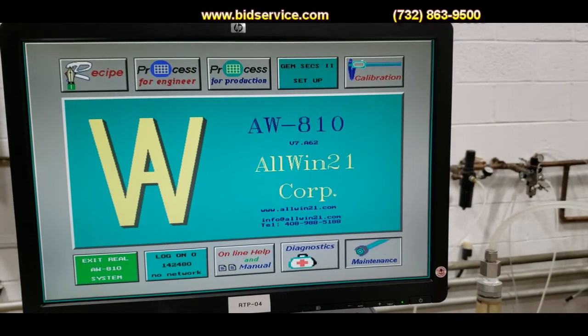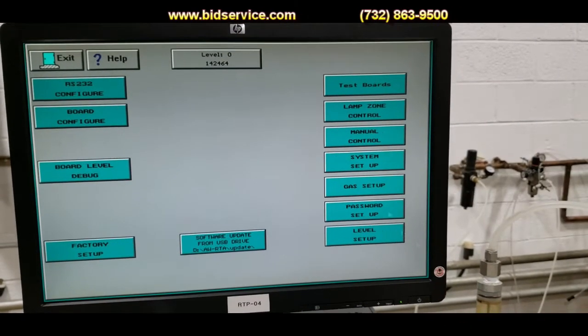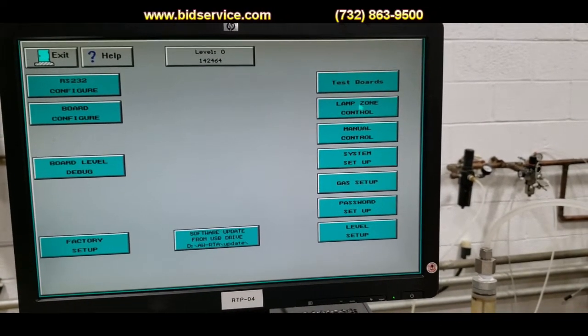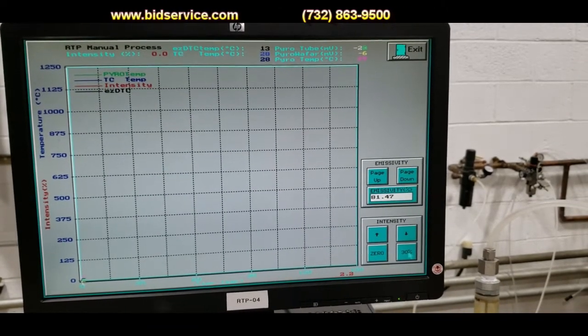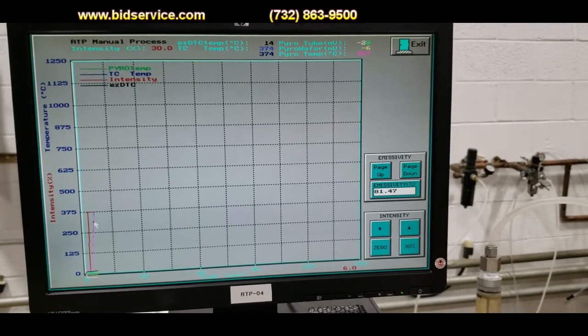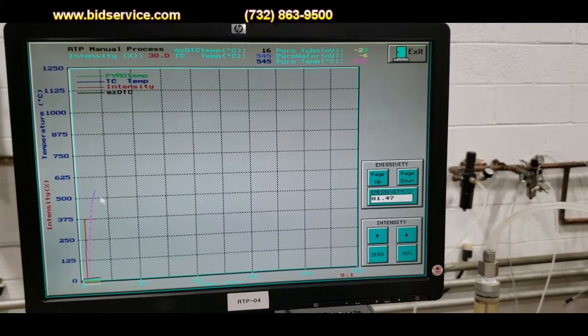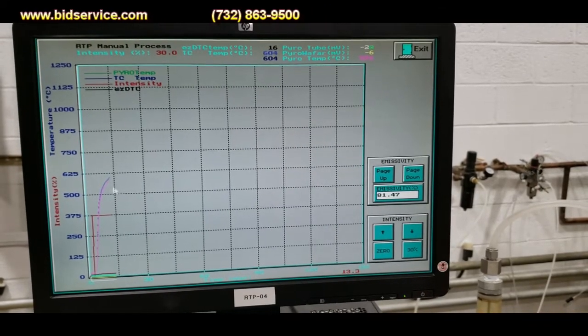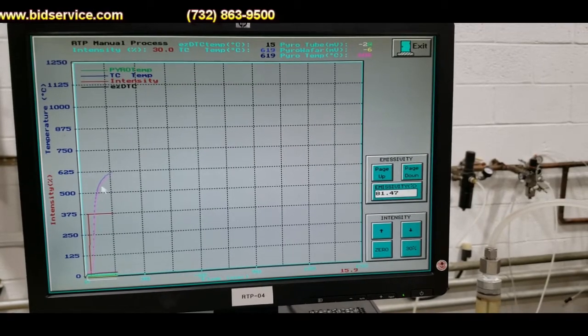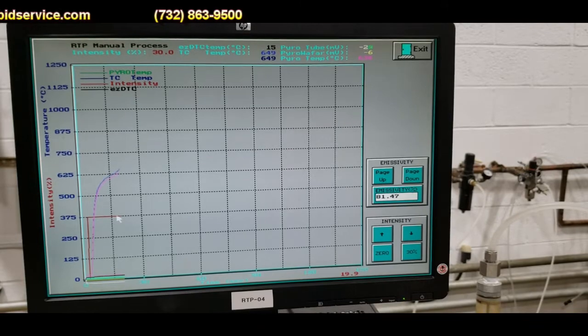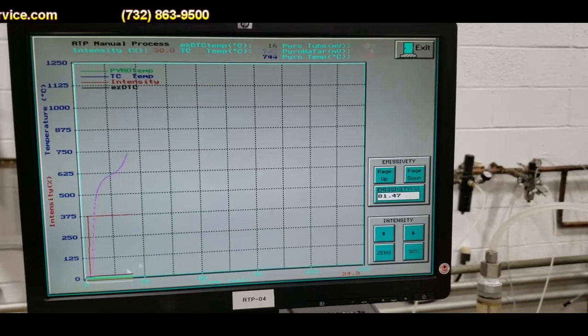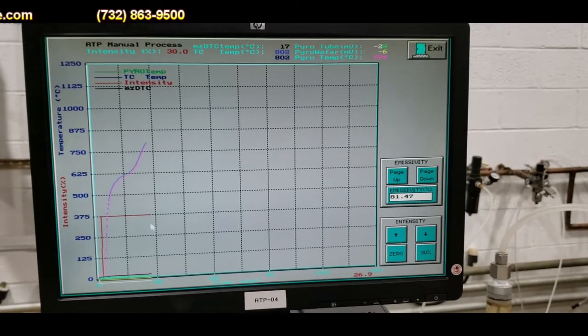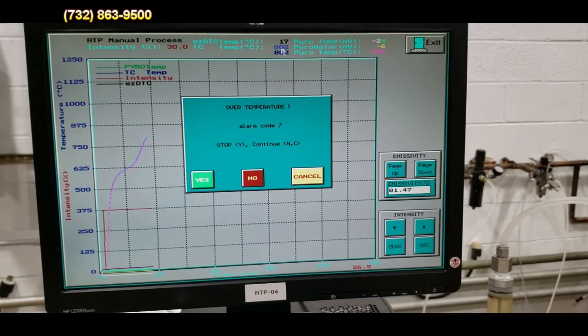And online help tells you how to operate everything. You saw the diagnostics and then you got the maintenance. And that is basically all the setups. The gas setups, the password, the level. And you can do like manual control. And you go ahead and go right up to 30%. And you will see that everything is spiking up over here. And here is your temperature. This is the dark purple. And the red right here is your actual set point set at 30. So these would be in increments of 10 each one of these lines. So that's 10, 20, 30. And of course it went in the over temp because it's past 800 degrees.